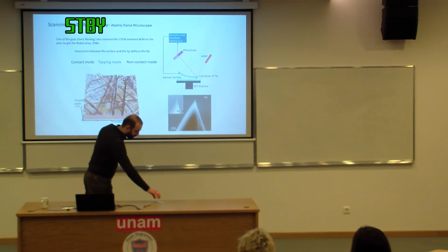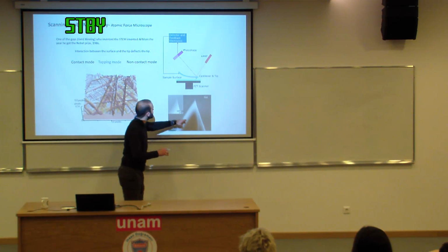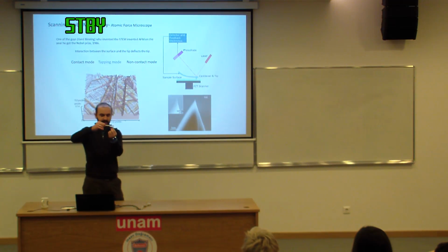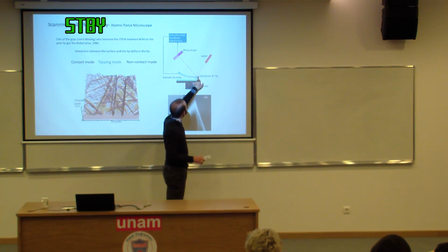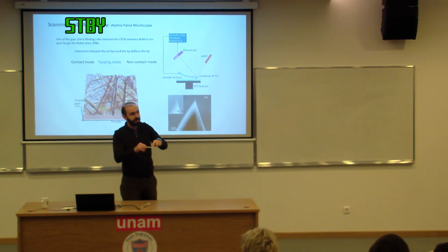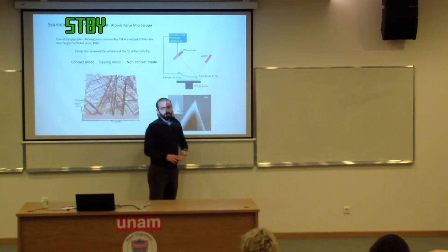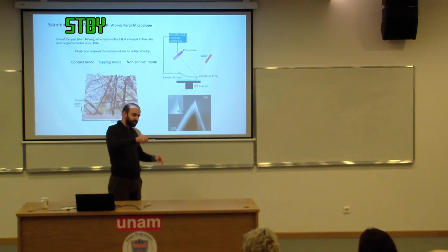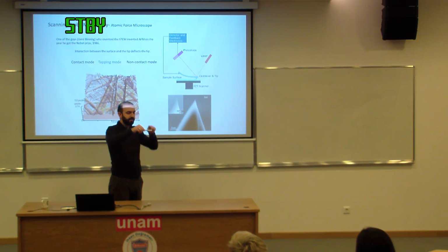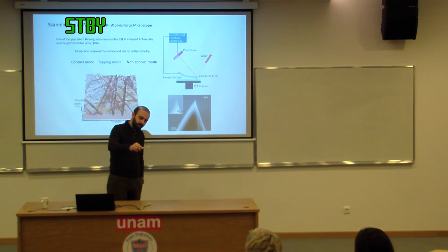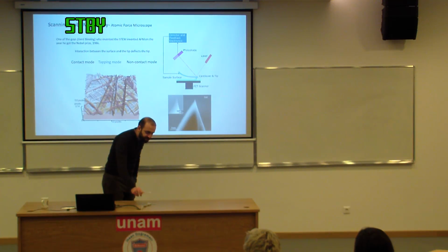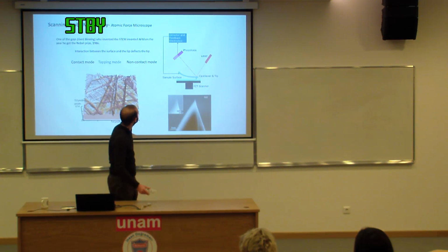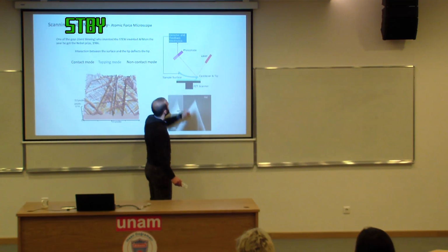And then you have this cantilever. This tip is attached on the underside of the cantilever. You have a laser shining onto the upper side of the cantilever, and it reflects to photodiode quadrants. In normal operation, there is no deflection of the laser when the cantilever is flat. The laser beam just hits the middle of the photodiode. When you lower this to the surface, because of certain interactions, which we'll talk about later, the tip starts flexing. And this flexing results in deflection of the laser.